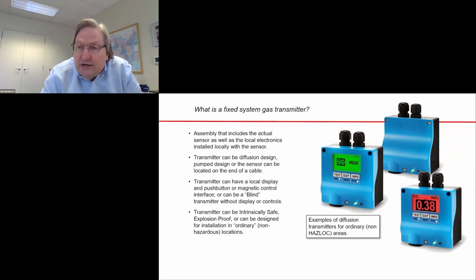If it is not an area that is characterized by the presence of combustible gas, then we would normally think of it as an ordinary or a non-hazardous location where the instruments still require an appropriate certification for electrical safety, comes from the same laboratory, different certification, still might be CSA, UL, DEKRA Exam. So it's still a certified product, but since it's not being used in a hazardous location, it's being used in an ordinary location. That's the certification that it carries.